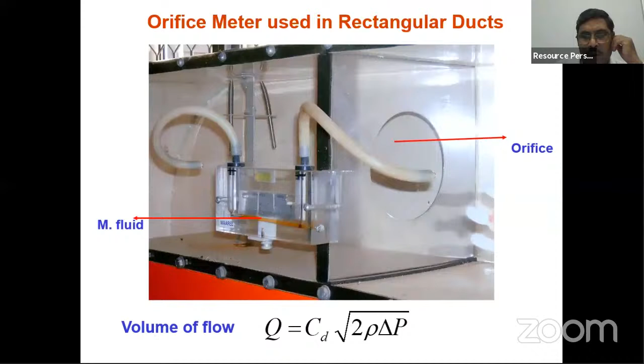In the case of the orifice, it's basically a thin metallic sheet that we have to insert in the flow. There will be an opening. In the orifice, you cannot recover the pressure loss. So the maximum value of the coefficient of discharge for the orifice flow meter is about 0.5 to maybe 0.6, not more than that. Therefore, when you go for the orifice, you need to precisely estimate the coefficient of discharge. Without that, you cannot use it. I think all these expressions will be known to you. Now you see here, whenever you use this meter, the coefficient of discharge is a function of velocity. So that means the Venturi, orifice and nozzle flow meters need to be designed for a particular flow rate.